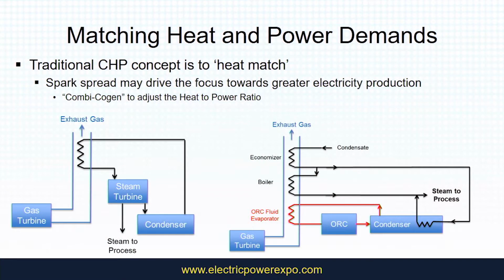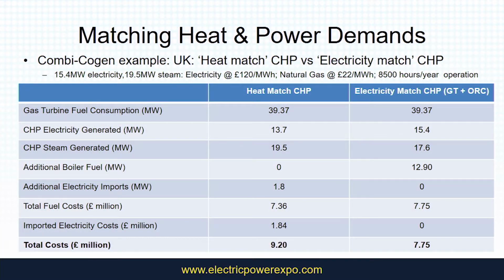Now, one of the things we found in Europe, though, is that your traditional heat match doesn't necessarily work, depending on the spark spread between your electricity price and your gas price. If you have high electricity prices, around about 5 to 6 times that of your fuel price on a dollars per kilowatt hour basis, you really should now try to tend your CHP plant more towards an electricity match than a heat match. And there we look at things like combi cogen with steam turbine with steam extraction, or a new concept that's hitting the streets in Europe is with organic Rankine cycle. Both of those give you slightly different heat to power ratios, but the mathematics, this is from a UK study that's ongoing at the moment.